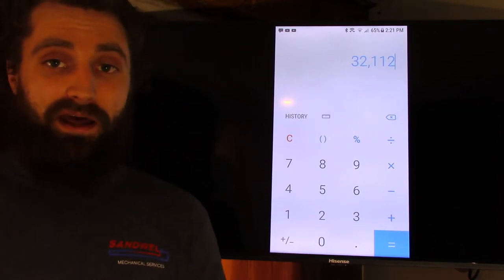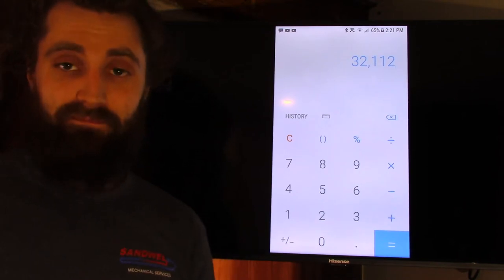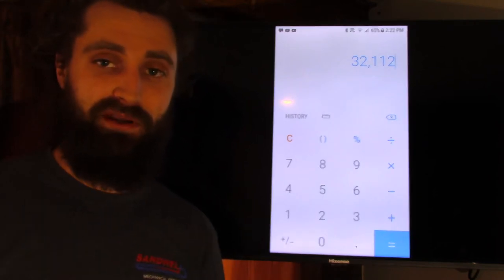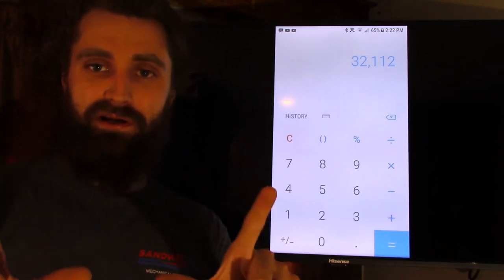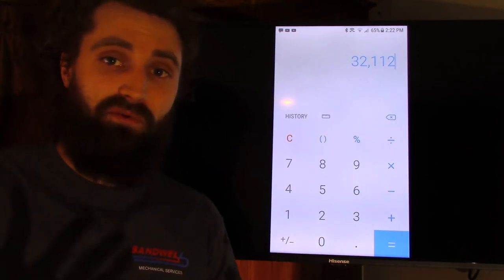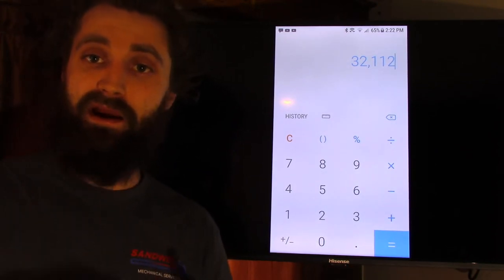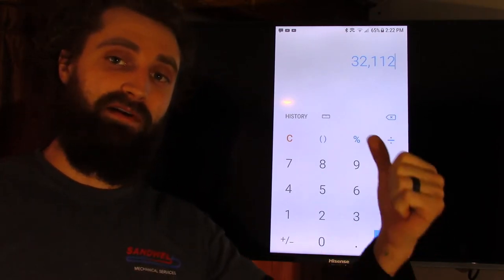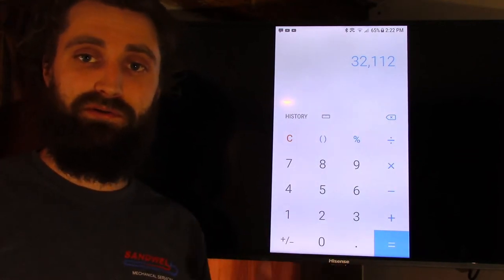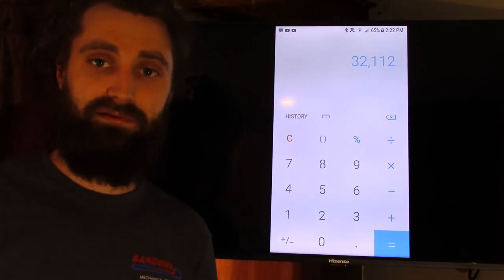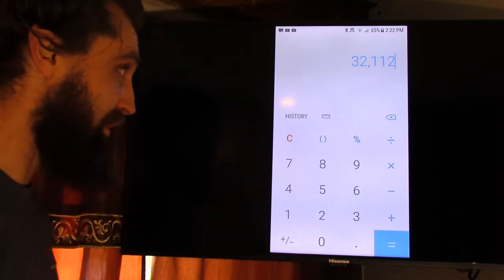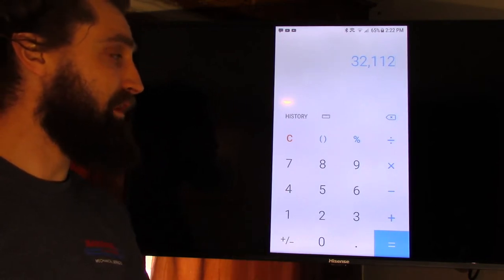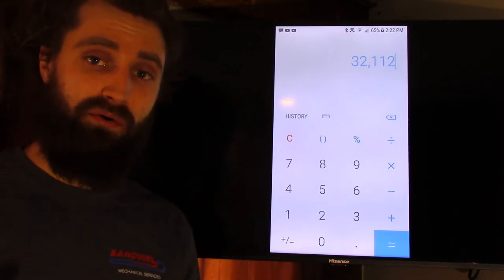So now we've got to look at something, okay? Why are we not removing enough latent heat? Why are we not removing enough sensible heat? I would say our sensible heat's pretty good. I mean, we're getting a 20-degree drop. Is there something wrong with the airspeed? Okay, do we need more air? Is our evaporator coil not hitting deep into the dew point and not removing enough grains of moisture? On that example, it very well could be. Okay, so that's some things you want to look at.